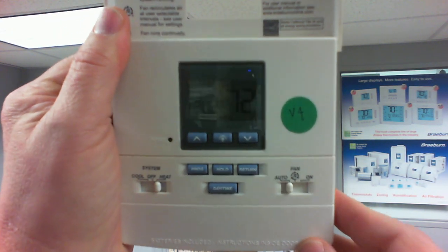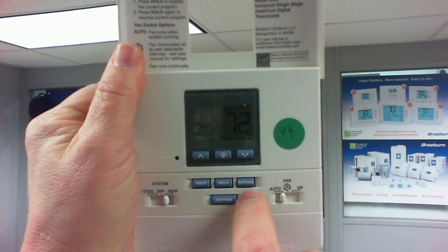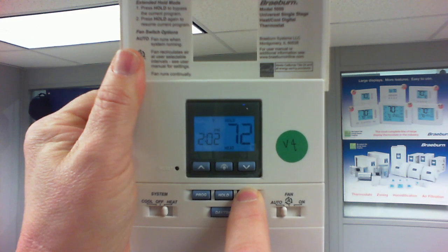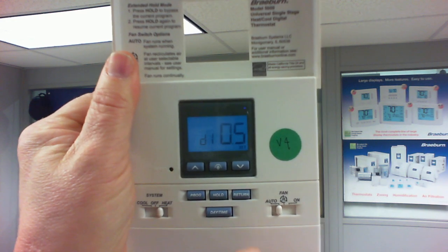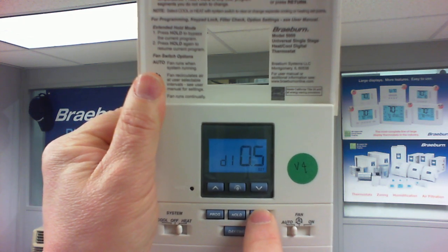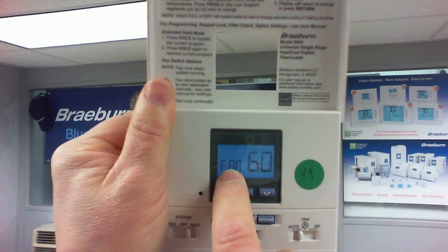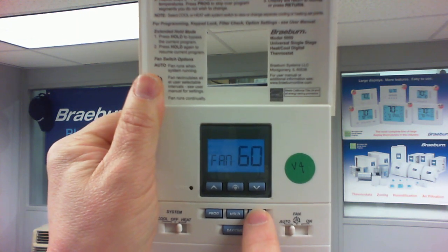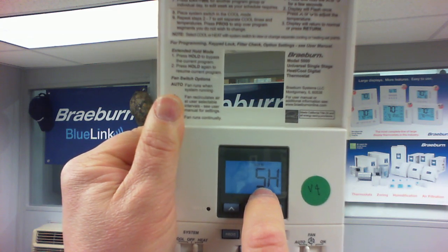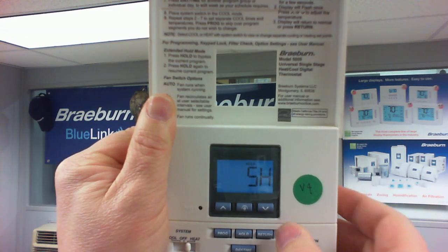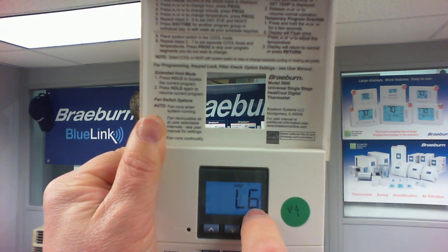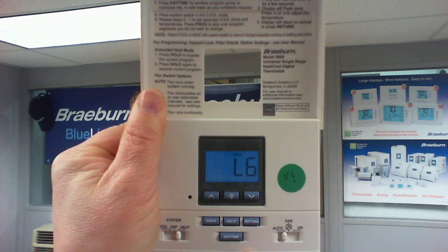To get into the advanced user menu on this thermostat, we're going to use the return button. We're going to press it, we're going to hold it down until we see the screen change. It's going to show us D1 and there'll be a number here. Pressing the return button again, we'll go to the second item in the menu, fan and a number. Press the return again, and this is going to say hold at the top, and you're going to see SH, which means short or 24-hour hold. And if we use our arrow key, we can change it to LG, which is long or indefinite hold.